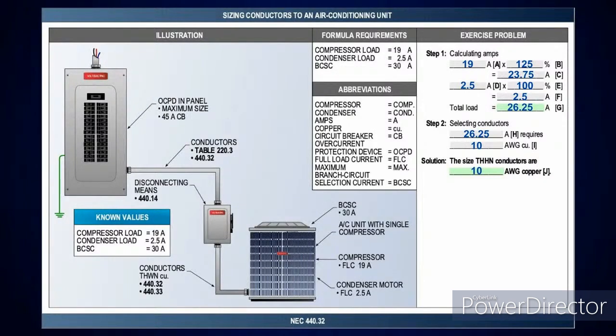Here's an AC unit. Now, when you deal with an AC unit, they're going to tell you right up at the front that you're going to use the nameplate value. First of all, let's discuss why you use the nameplate value. Well, the reason is because this is an appliance. In other words, it's a listed assembly. It's all contained in one. So you're going to use the nameplate value right here. I have a compressor of 19 amps and a condenser of 2.5. That is the main important information you need here.